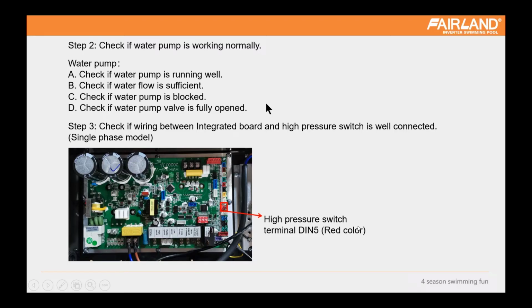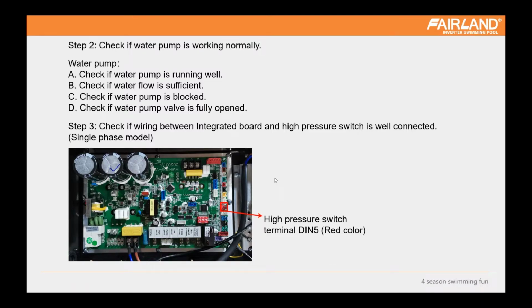And finally, because sometimes the customer is also not so clear about what is happening, they return the units. We say okay, return it and install it in your warehouse with another pipe, and you will find that all of the heat pumps run well. It's not a heat pump problem. This is the final step, because moving the heat pump back to your warehouse, installing it and trying to run it also takes a lot of time.